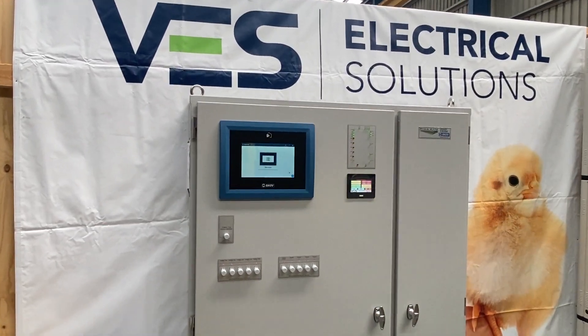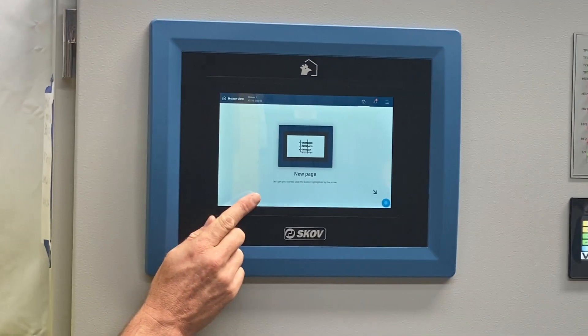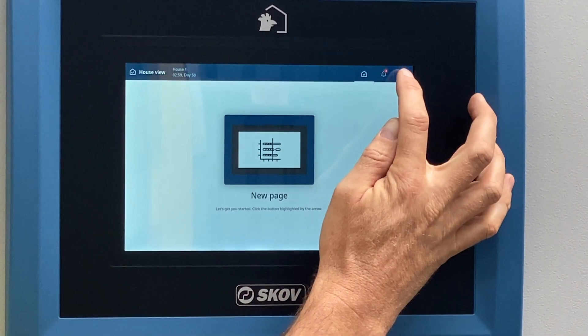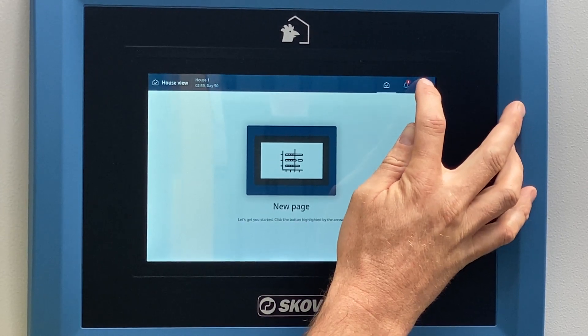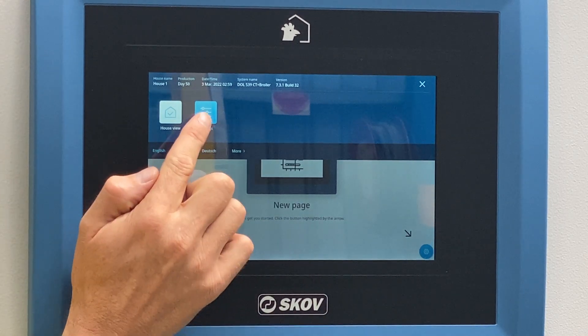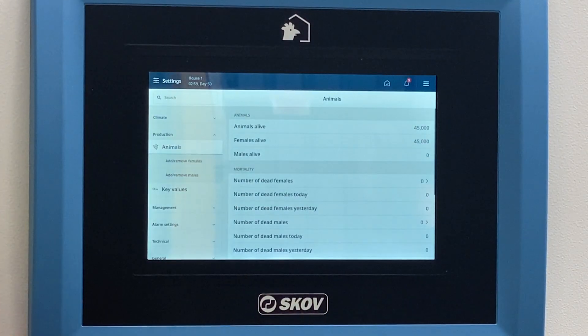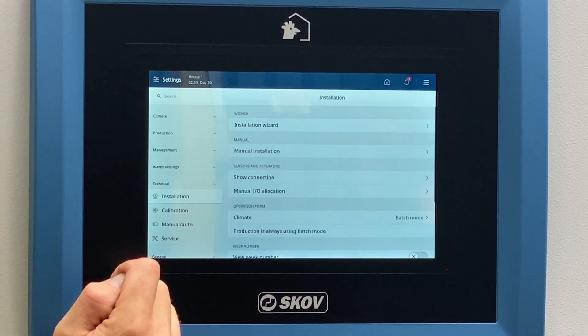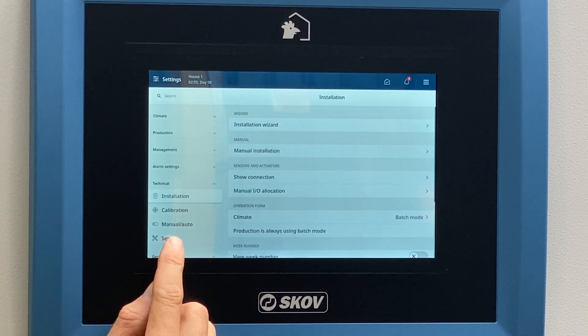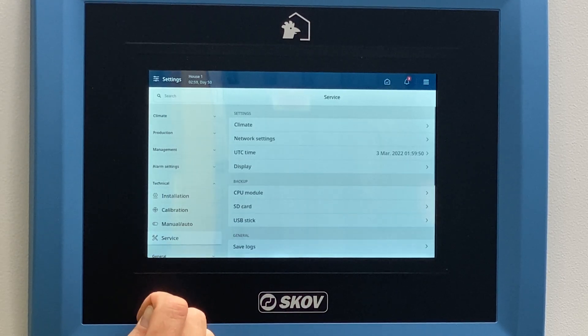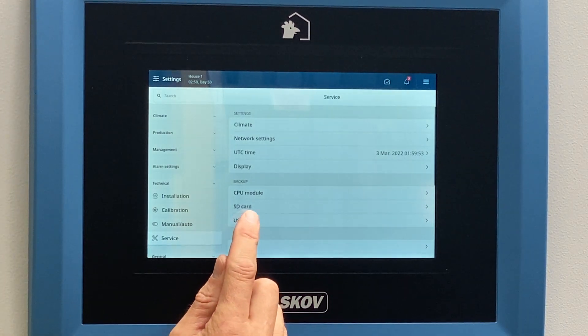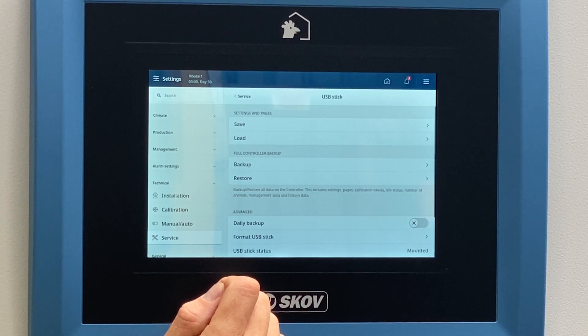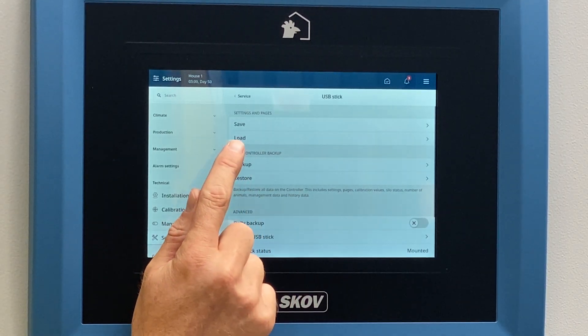Close that door and with the controller powered up, we're going to move across and hit the icon with the three white buttons in the top right-hand corner. After that we're going to select the settings icon with one push. You'll see in the left tab there's a tab called Technical — click on Technical once. That will bring down a drop-down box where you select the Service icon. From here you can see on the right we have another icon called USB Stick — we're going to push that once. It will bring up another menu where you can see the option to load your program.